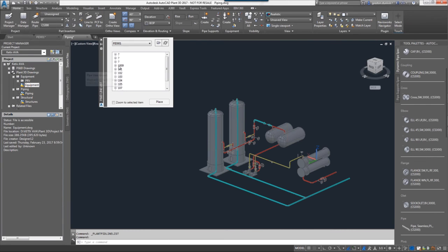Now, what this does is look at anything inside of your P&IDs, and you can directly pull off the lines and any associated valves. So you can see, for instance, line 101 is a 10-inch carbon steel 300. It looks like it's a general process. And we've got it running off of nozzle M3 on tank 101, and going to gate valve HA101. Right here alone, this is where you're going to start your link. It'll also link over things such as equipment.